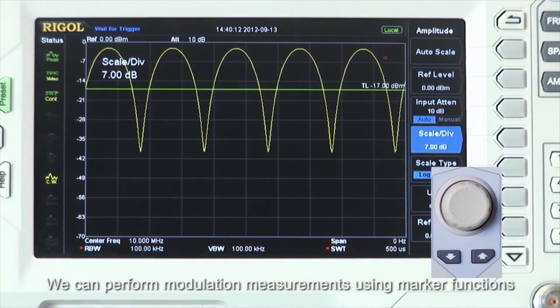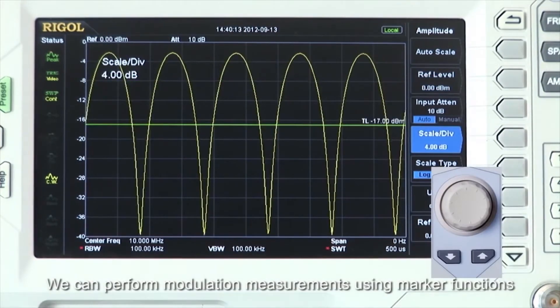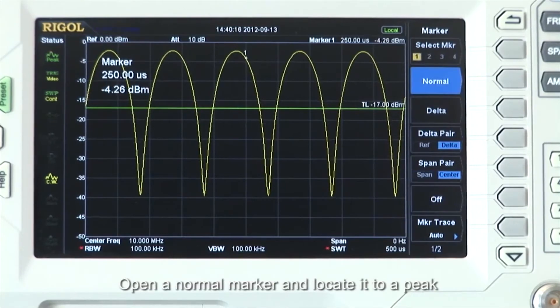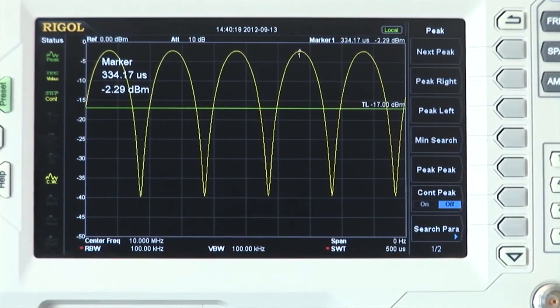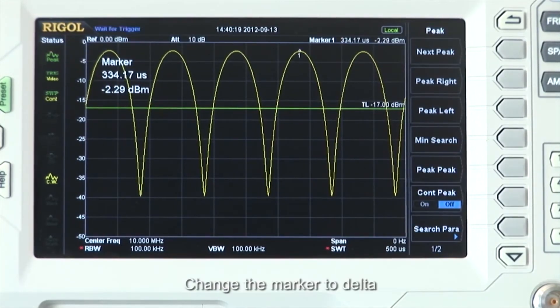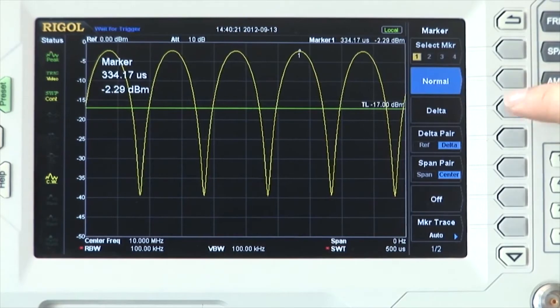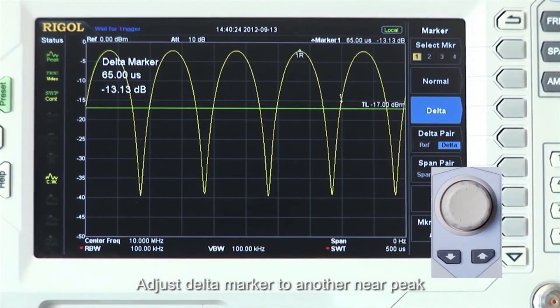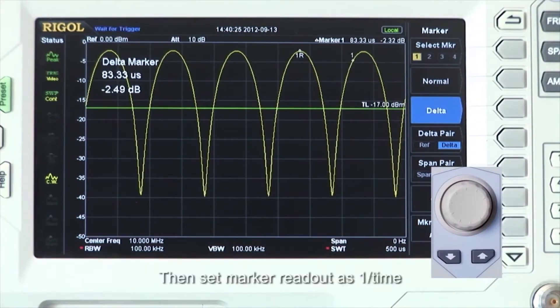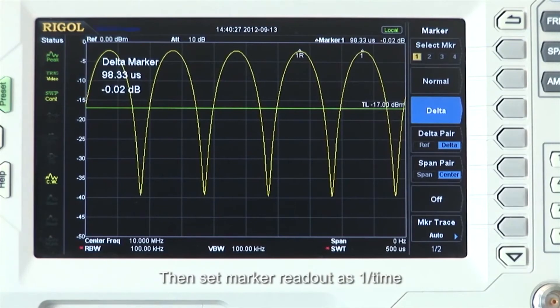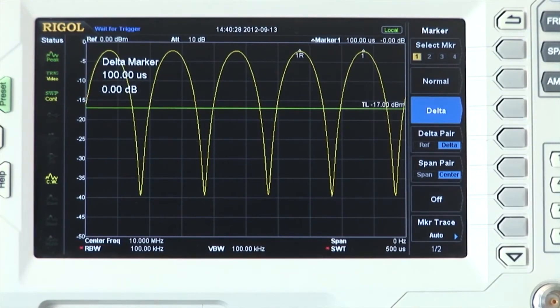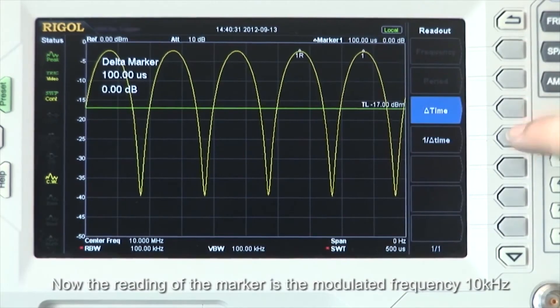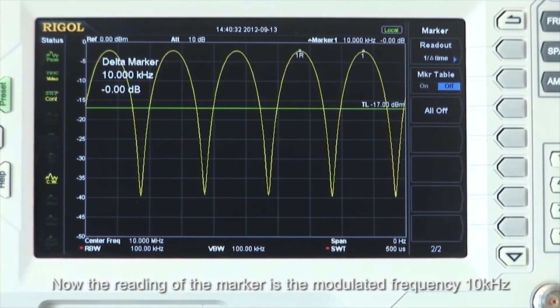We can perform modulation measurements using marker functions. Open a normal marker and locate it to a peak, then change the marker to delta. Adjust the delta marker to another nearby peak, then set marker readout to 1-over-time. Now the reading of the marker is the modulated frequency of 10 kHz.